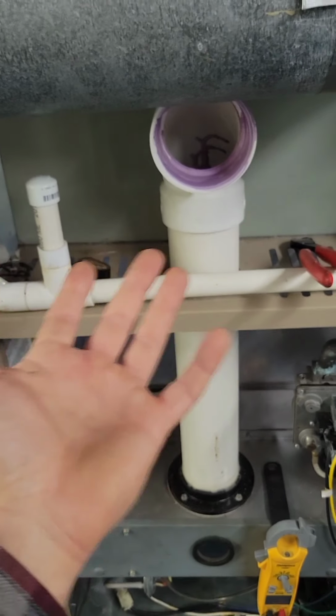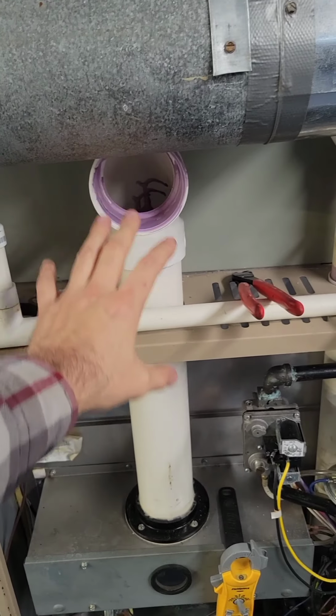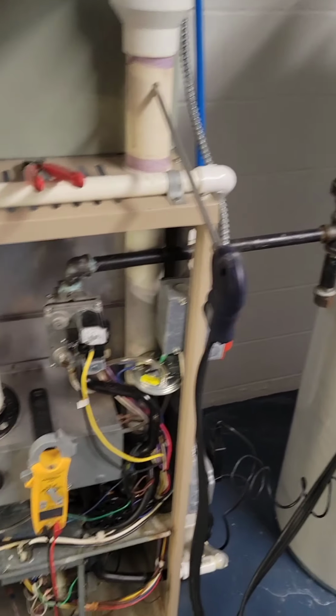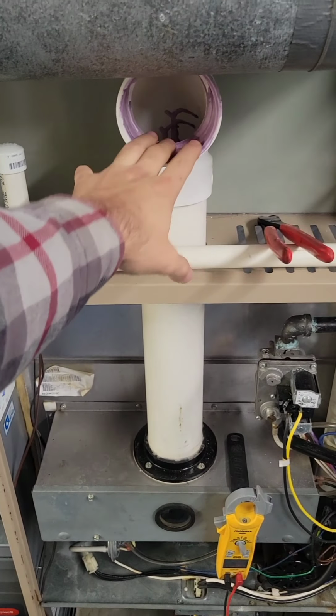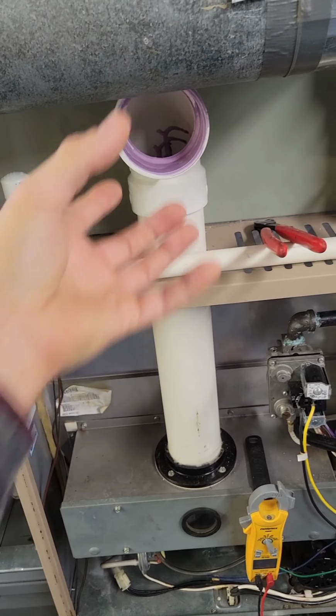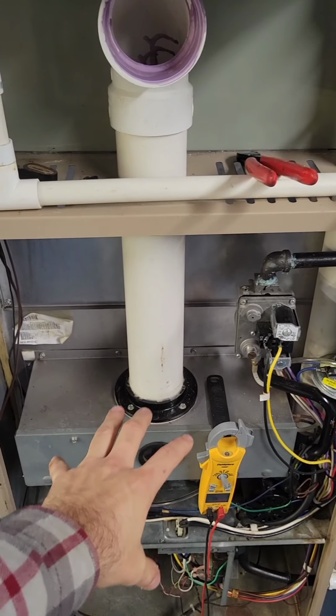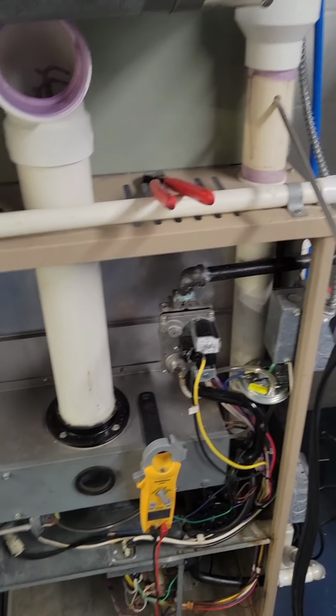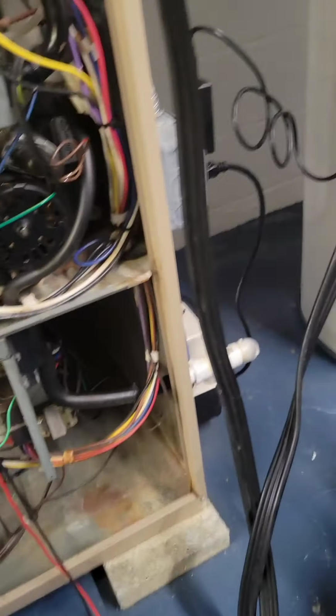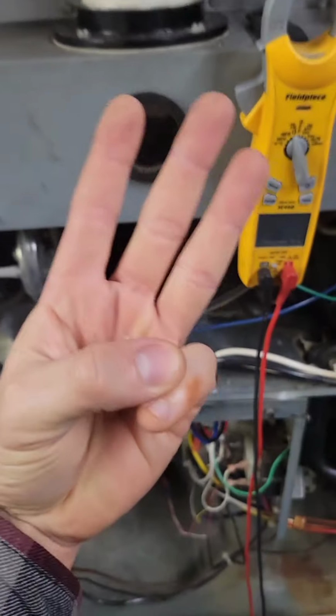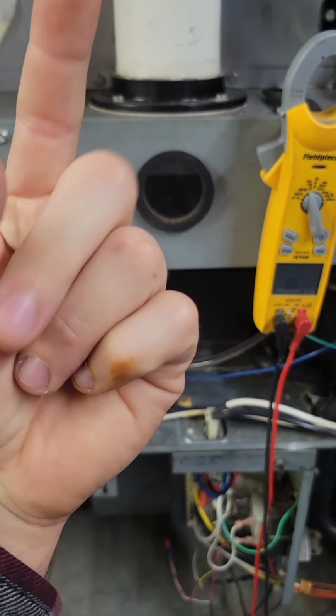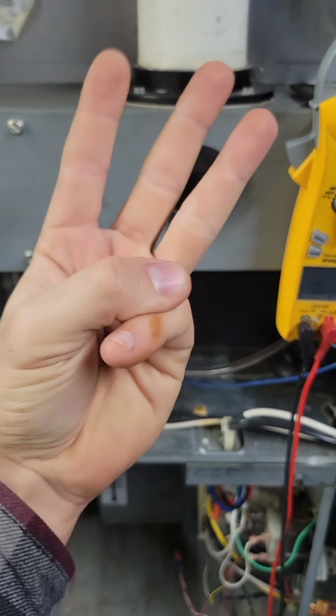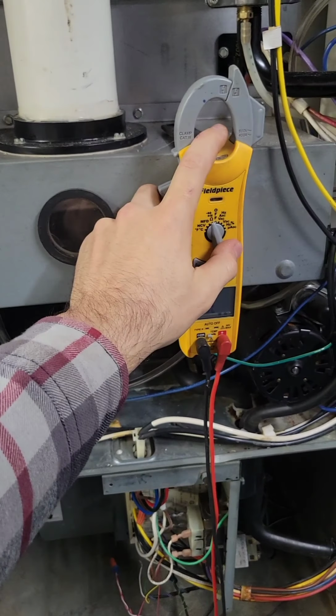So certain things are going to be a little bit different. But you can see in this one, they are actually using the combustion air from within the basement, which is sufficient enough. I mean, it's a wide open basement. It's not finished or anything like that, to allow it to combust. So we're grabbing the air from here, sending it down to the combustion chamber, and that's how we're combusting the air, right? So what do you need for combustion? There's three things you need for combustion, right? So you need fuel, you need a spark, and you need air. Those three things make up your combustion sequence.